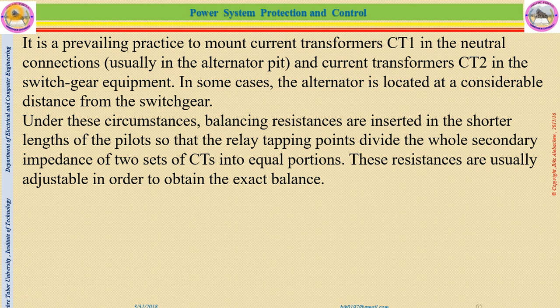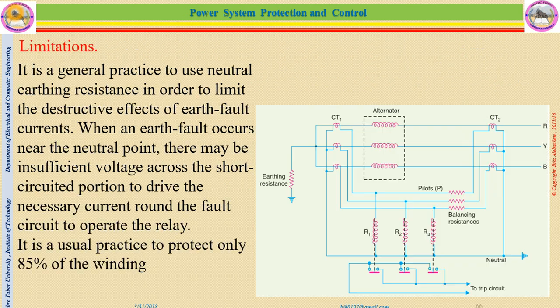In some cases, the alternator is located at considerable distance from the switchgear, and under the circumstance, balancing resistances are inserted in the shortest length of the pilot, so that the relay tapping point divides the whole secondary impedance of the two sets of CTs into equal portions. Those resistances are usually adjustable in order to obtain the exact balancing, and they are called balancing resistance because the two pilot wires may not be equal in resistance value. Now, this is the limitation of this balancing or differential relays.